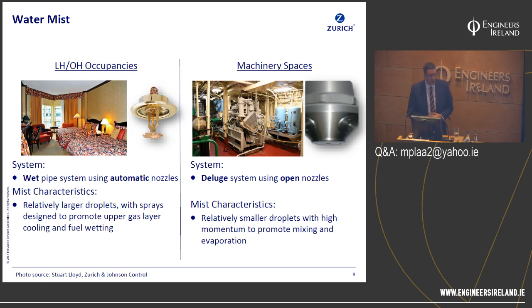Now we're moving from the traditional domain of the machinery space era, from the marine environment, where there are well-established IMO protocols, for example, and where we can be confident that water mist, within the bounds of the fire test certification for ships' cabins, corridors, machinery spaces, combustion, diesel generators. We know the local application, we know the history of that, but we're now moving over to the light hazard, ordinary hazard occupancy. And this is where we need to be careful where we move to the land-based applications. And again, I'll support some of my arguments with some case studies.